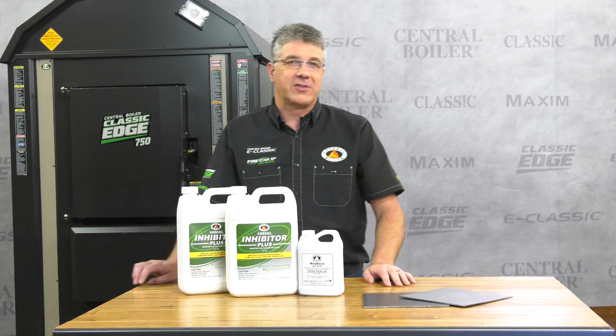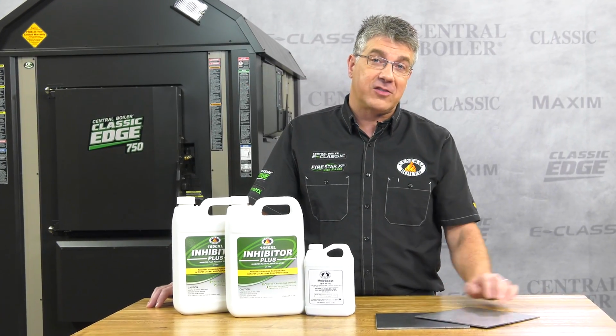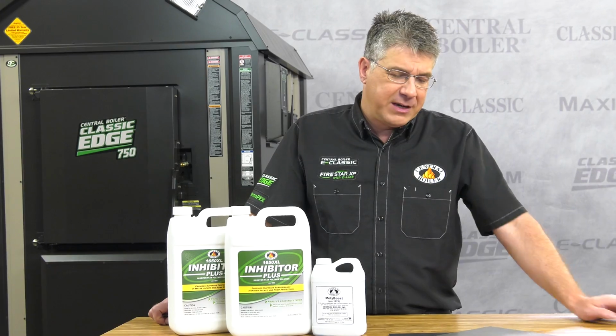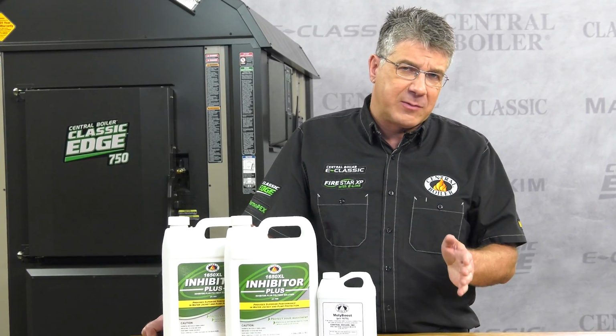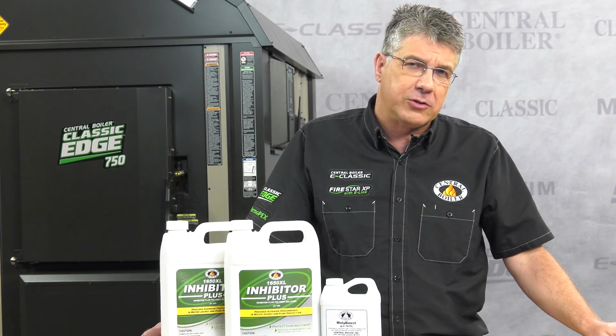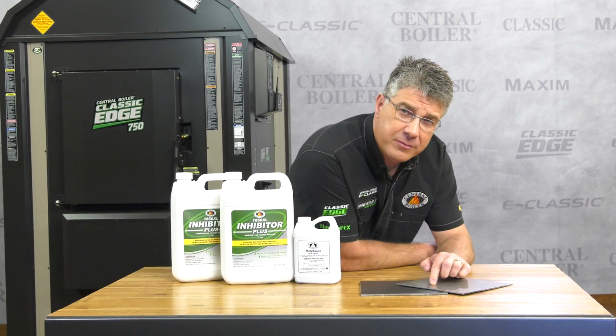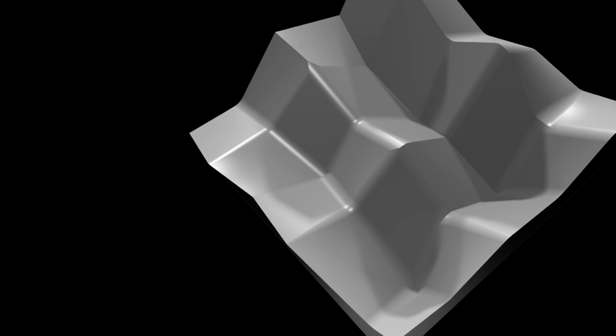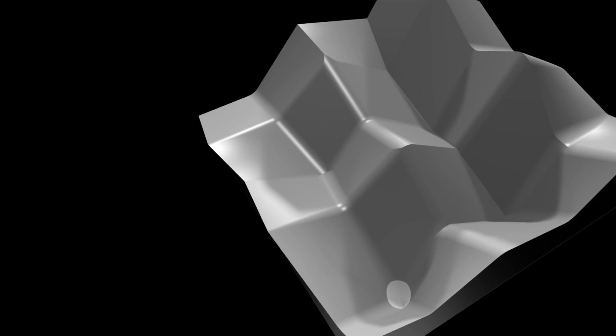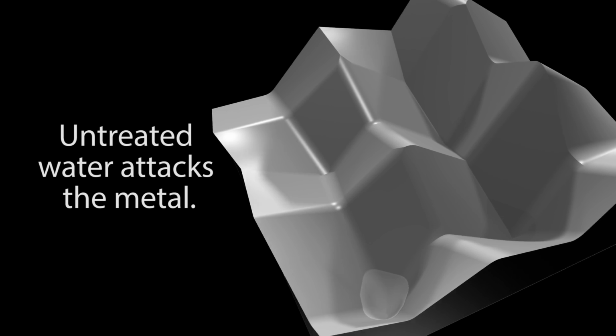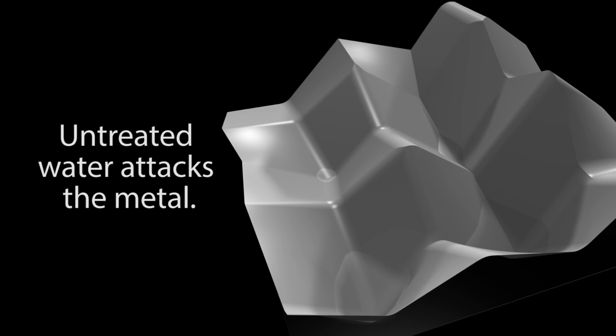Central Boiler uses high-grade steel and stainless steel in their outdoor furnaces. But even high-grade metal is susceptible to corrosion if untreated water is used. Steel feels smooth, but under a microscope, it's actually a mountainous range of peaks and valleys. If untreated water gets in a valley, it may never get out. This untreated water attacks the metal. Corrosion can start and lead to failure of the metal.